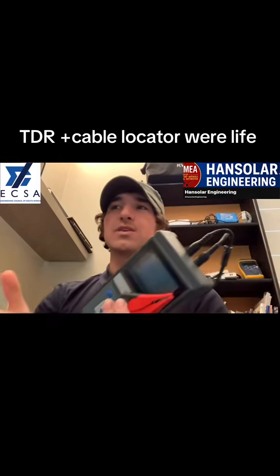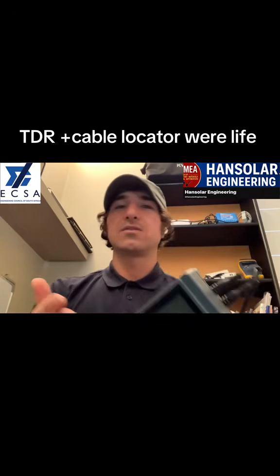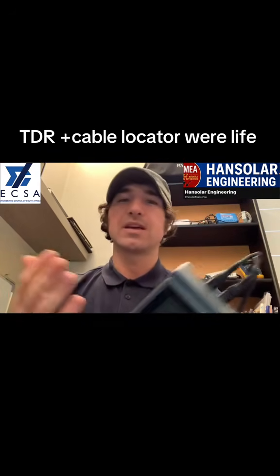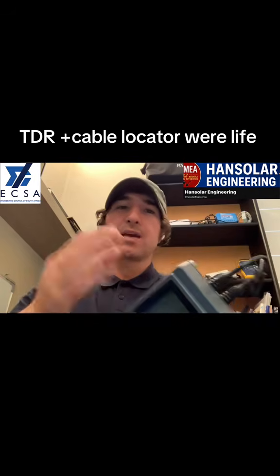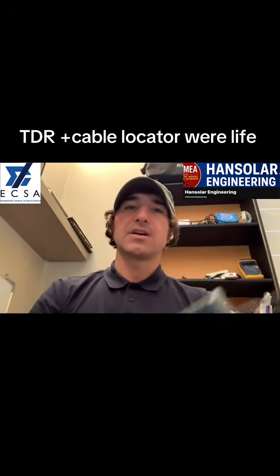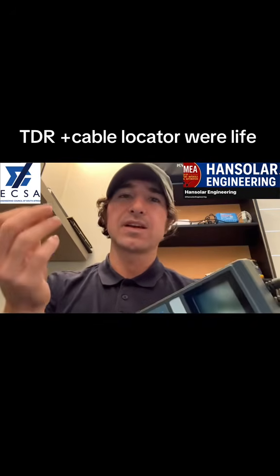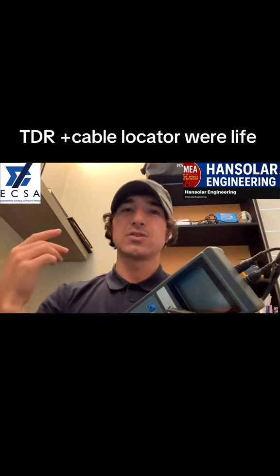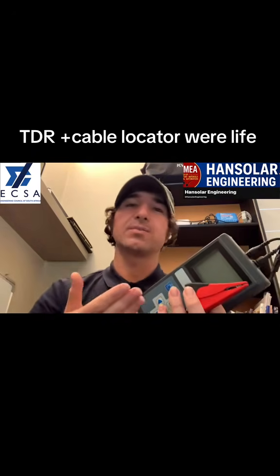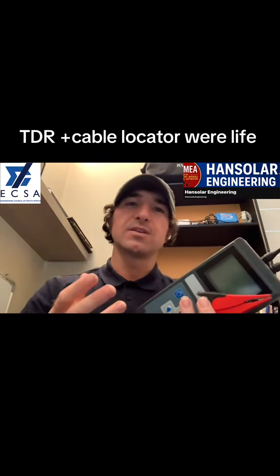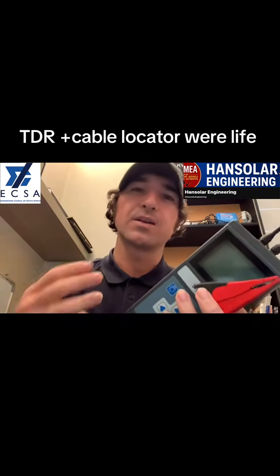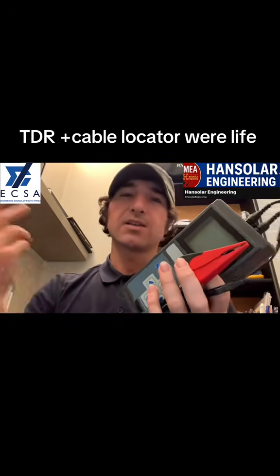Of course, there are reasons to use a megger, a thumper, and then use this, right? If there isn't a dead short, sometimes the cable can look alright on the TDR. It might have a very little reflection there. And of course, when there's a short circuit between two cables, you can also pick it up on this. It has an inverted input where it would see that the short signal came back.